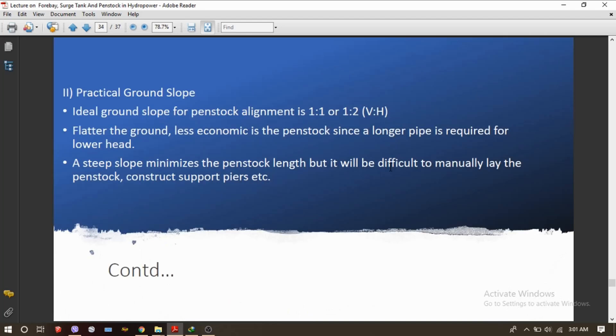The second point is practical ground slope. The ideal ground slope for penstock alignment is 1:1 or 1:2 — that is, vertical to horizontal. This is the practical ground slope, but different ratios can be adopted according to the topography and economic feasibility of the project.